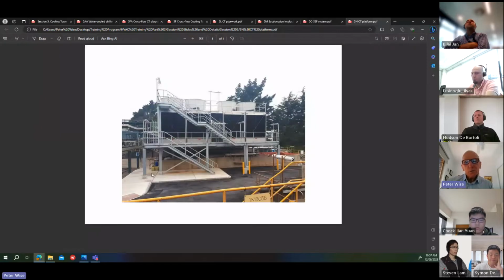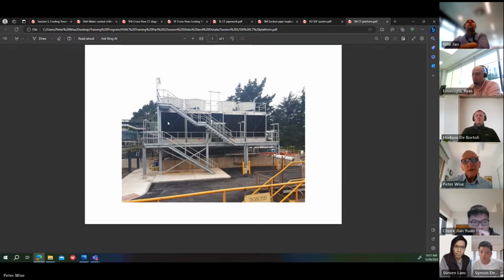Here's one with multiple levels. So the bigger the cooling tower gets, the more levels you're going to need for access. So this one's got a lower level, which will get you access to the fill at the lower level, the water basin. Then you may need to get, or you need to get up to the top as well. So you've got access to the water distribution basins and the fans. Maybe a little bit hard to see, but I'll see if I can make that a bit bigger.